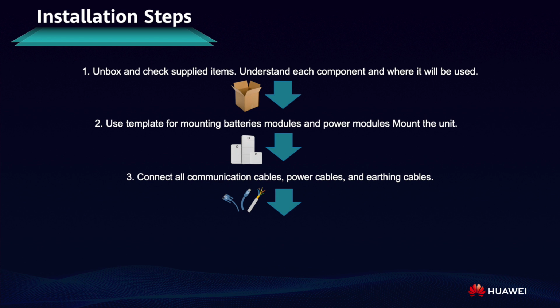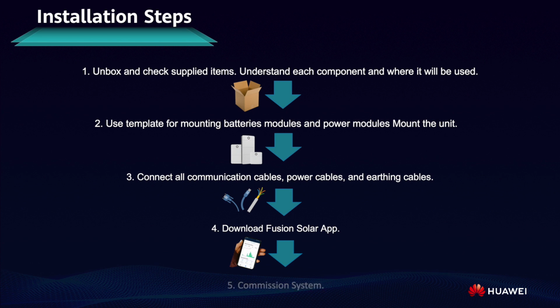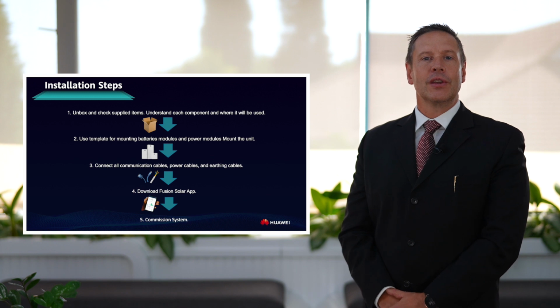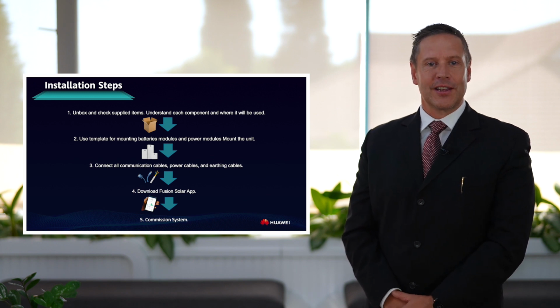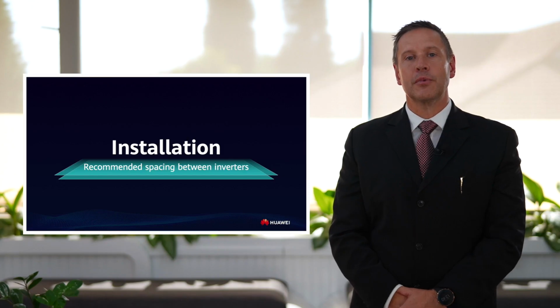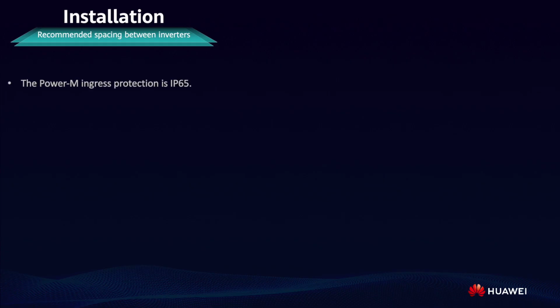The 4th step will obviously be to download the Fusion Solar app. You'll be using the Fusion Solar app to do commissioning of your system and to monitor the working of the system at a later stage. Installation. Recommended spacing between inverters. The Power M ingress protection is IP65. For this reason, there are no external fans.